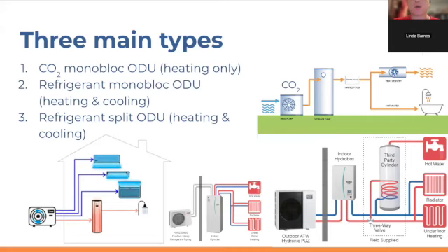Now, in Europe, there are some refrigerant monoblock outdoor units in that second category that use propane as a refrigerant. Propane has a much lower global warming potential than R32 and R454B, but propane is highly flammable. And even though propane is used in gas barbecues all the time across the country, and people seem fine using barbecue grills, in the HVAC world, there's great concern about propane. And so, therefore, here in the US market, there's currently no approved use of propane in even monoblock outdoor units.